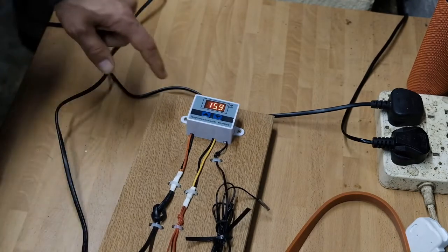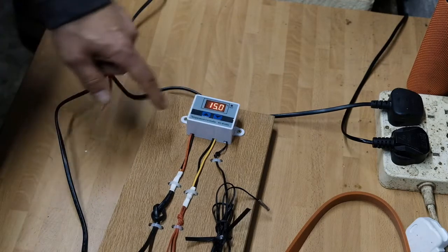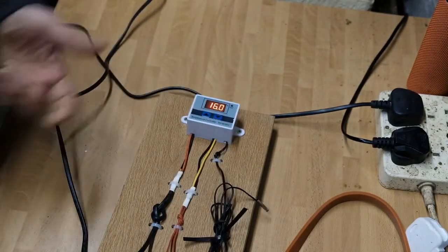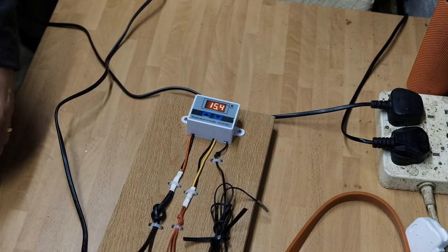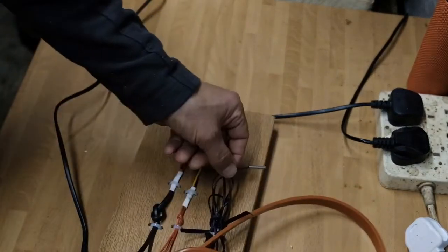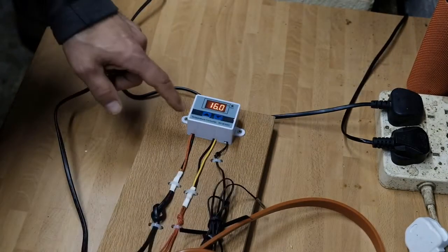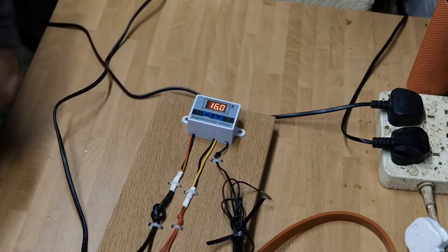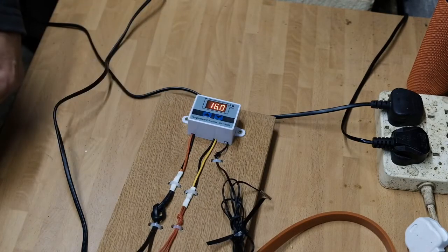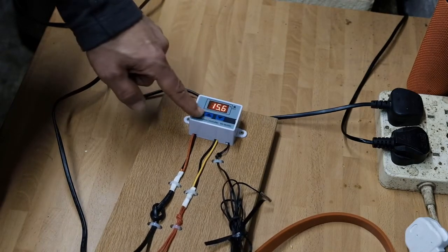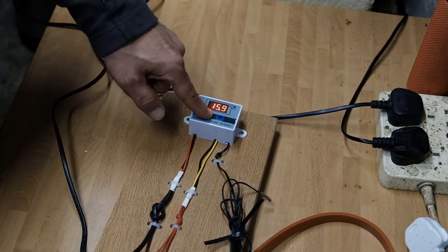Let me demonstrate. I'll reset it. If it's currently 16 degrees, I'll set it to come on at 15.9 and go off at 17. So hold down that button until it starts flashing. There's up and down arrows on here, so it'll come on at 15.9 and go off at 17.